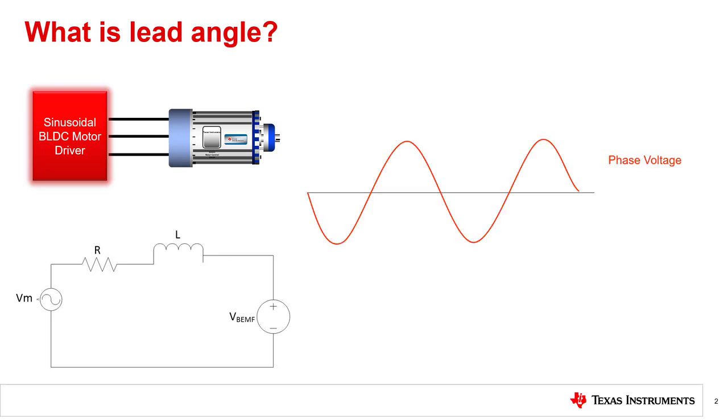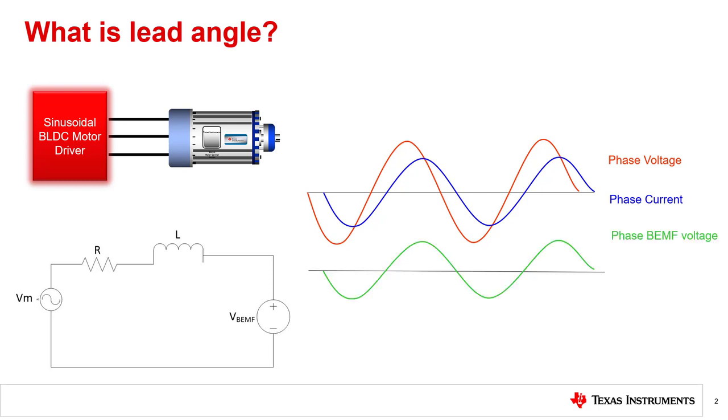Phase current of the motor lags the phase voltage because of the inductance of the motor. To achieve optimal efficiency, the phase voltage should be applied in advance compared to the back EMF voltage and must be adjusted to keep the back EMF voltage aligned with the phase current. This difference between the applied phase voltage and the back EMF voltage is known as lead angle.